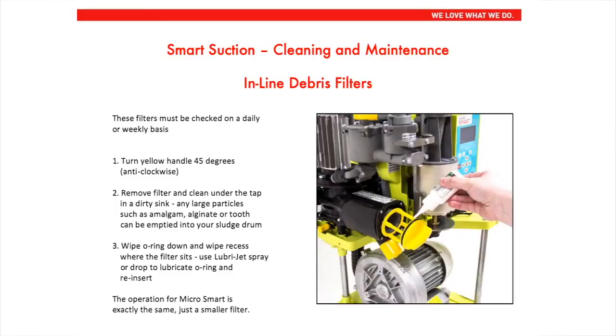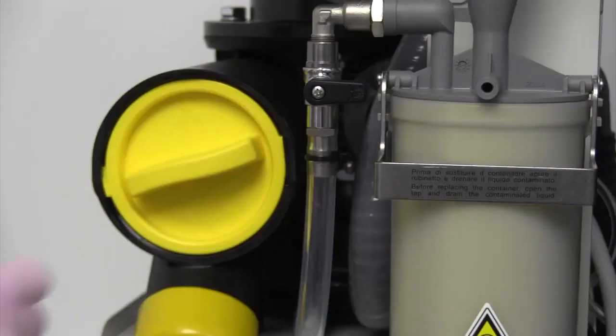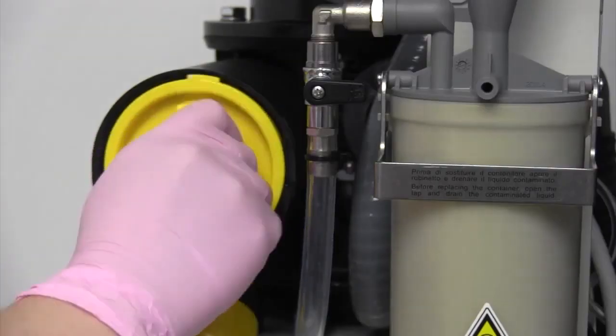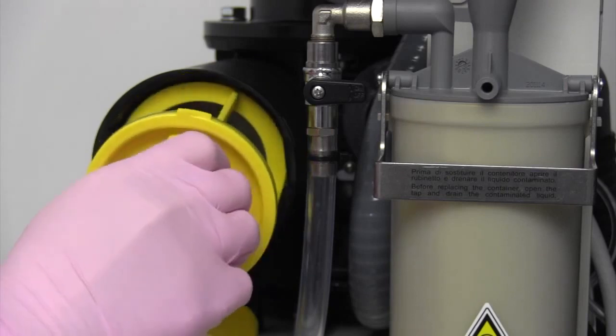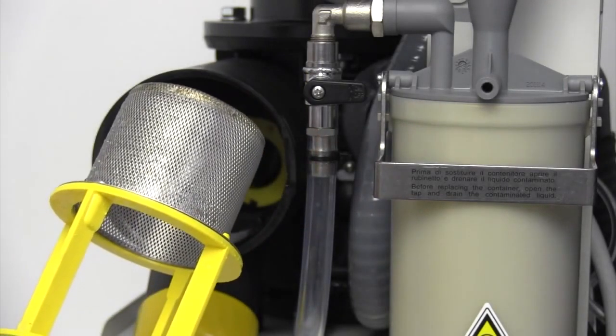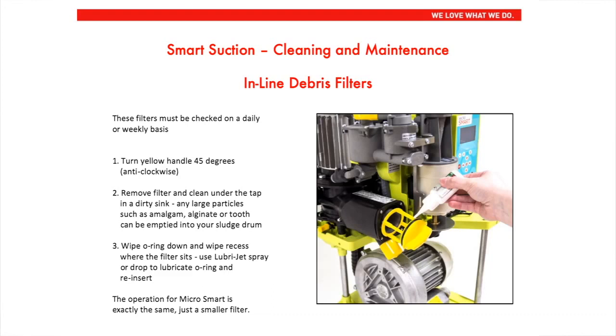Smart suction cleaning and maintenance, inline debris filters. These filters must be checked on a daily or weekly basis. Firstly, turn the yellow handle 45 degrees anti-clockwise. Number 2, remove the filter and clean under a tap in a dirty sink. Any large particles such as amalgam, alginate or tooth can be emptied into your sludge drum.